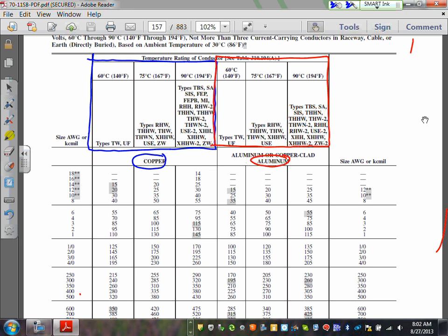Again, if you end up working for a company that only uses aluminum because they have a customer who cannot afford copper, you start cutting costs and using aluminum conductor. They're safe enough, yes, sir. When I was working for Parsons this summer, they used aluminum for the service conductors. They were 750 kcmil. Aluminum. Mm-hmm. Absolutely. Again, you're working for a contractor, unless the engineer tells you copper.